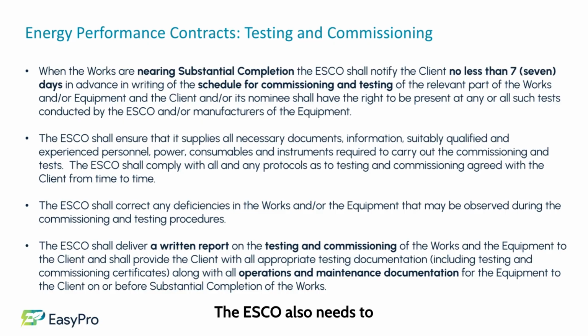The ESCO also needs to correct any defects or deficiencies in the works or equipment observed during the commissioning and testing procedures, and must deliver a written report about the testing and commissioning to the client. They have to provide appropriate documentation, including all operation and maintenance documentation, before the phase called substantial completion of the works.